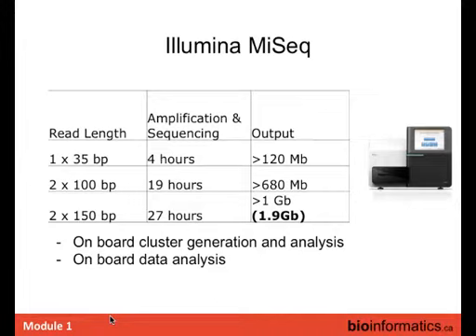The MiSeq is the baby HiSeq. The HiSeq produces around 700 gigabases; the MiSeq is a smaller version, specced around 1 gigabase — we typically get around 2, with an upgrade expected later in the year to reach around 7 gigabases. The nice thing is fast turnaround: it does onboard cluster generation and onboard analysis, making it a complete genome center in a box. You put your library in, it makes clusters, runs, and completes analysis in about 30 hours. It does long read lengths — 2×150 base pairs.